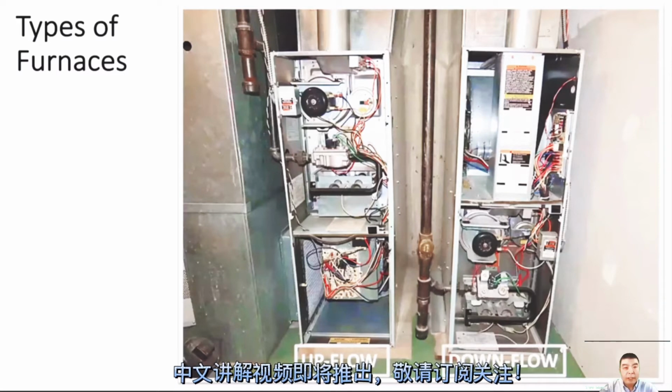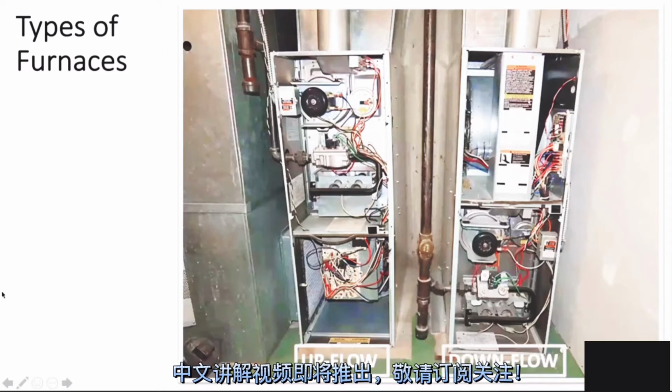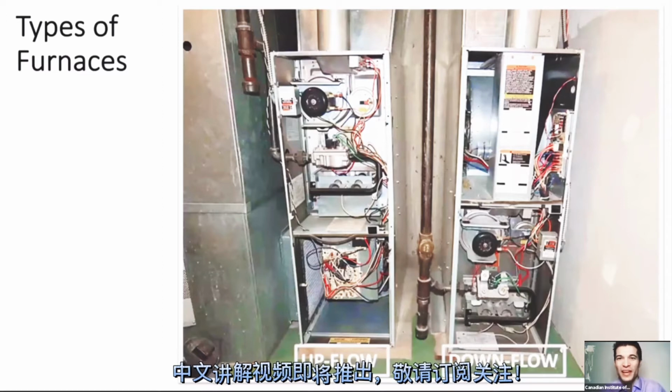Okay, thank you. When I first moved into this place, my furnace required a 5-inch wide filter, and it had a 1-inch wide filter, and it was sucked halfway into the plenum. So not good. Yeah, very common, absolutely. And some older furnaces have hidden compartments. I've definitely come across furnaces that have never had their filter changed in 50 years because people didn't know it was installed in the back of the unit, like a low void typically.